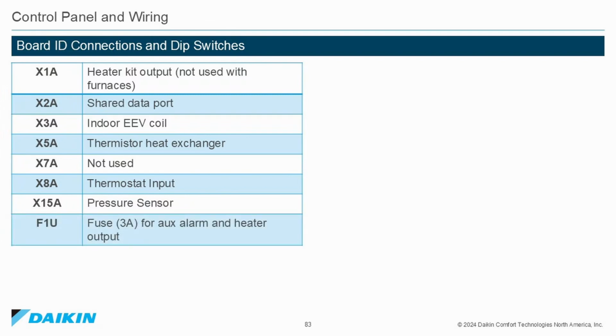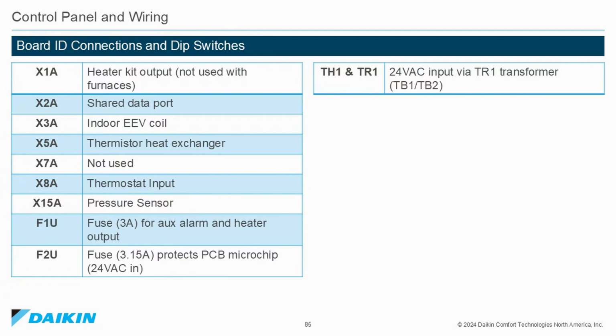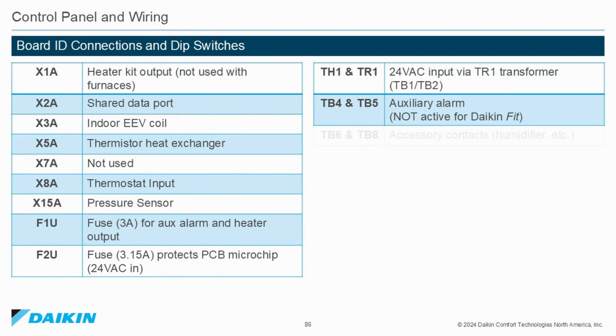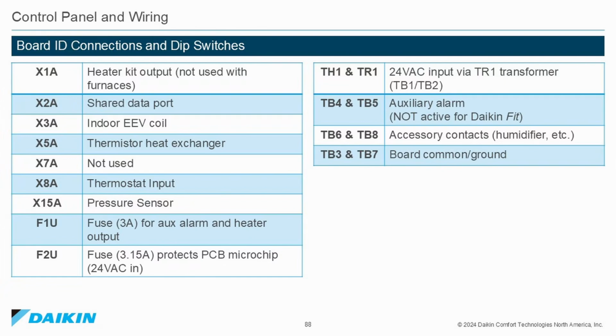F1U, fuse 3 amp for auxiliary alarm and heater output. F2U, fuse 3.15 amp protects the PCB microchip 24 volts AC in. TH1 and TR1 are the 24 volt AC transformer input via transformer 1, TB1, TB2. TB4 and TB5, auxiliary alarm, not active for a Daikin FIT. TB6 and TB8, accessory contacts, humidifier, etc. TB3 and TB7, board common, ground.